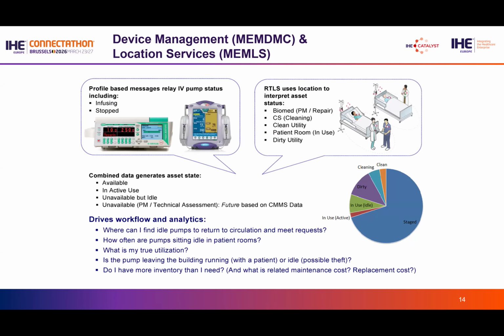Next one. So moving from the patient relationship to a focus on the connected devices, we have our last profile for today, the medical equipment management profile, or MEM. MEM covers 2 areas, including device management communication and location services. So MEM is focused on the management and health of the devices that we're using to care for the patients. These profiles produce information like device status, like whether charging, the charge level, the location, or device availability.